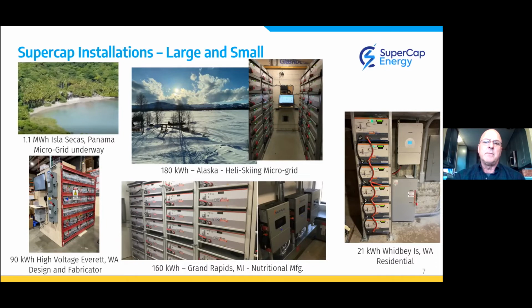The one in the center is an off-grid heli skiing location in the Tordrillo Range of Alaska, about an hour and 10 minute flight by bush plane out to the site from Anchorage. We swapped out about 15,000 pounds of lead acid batteries that were no longer functioning after about 3 years with 48 supercapacitors, which doubled their capacity in the same footprint but reduced their generation runtime significantly. Of course, the generator used to run 24/7 because the batteries were no good. But when we left, the generator runs about 7 hours a day just to recharge the capacitors.